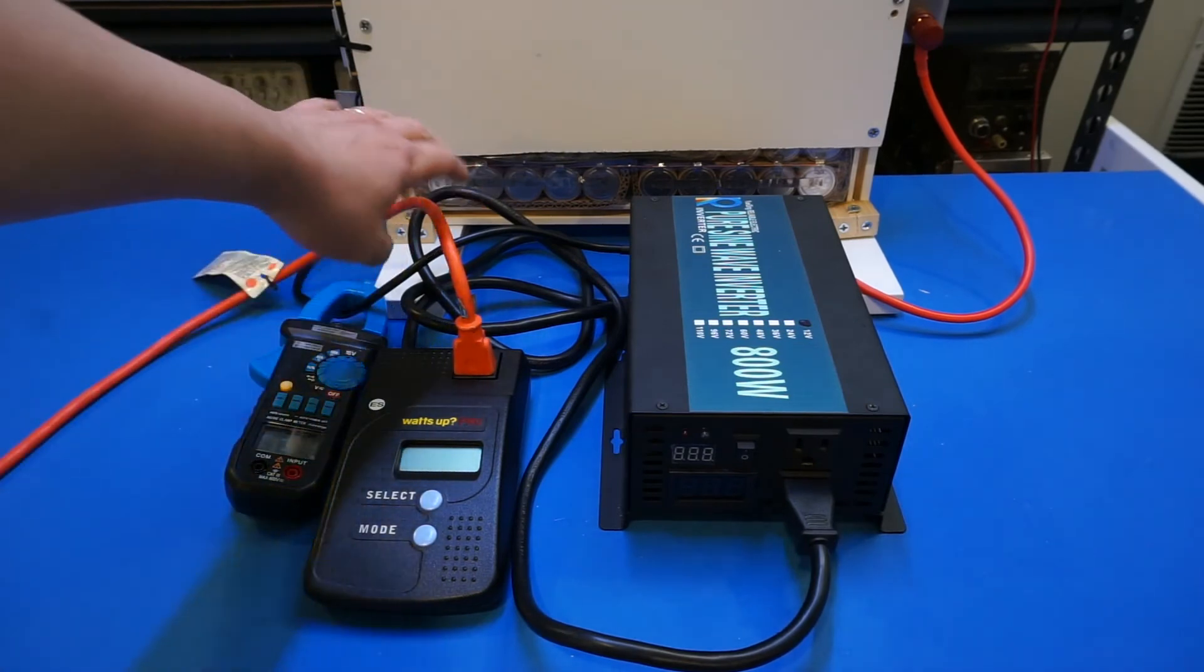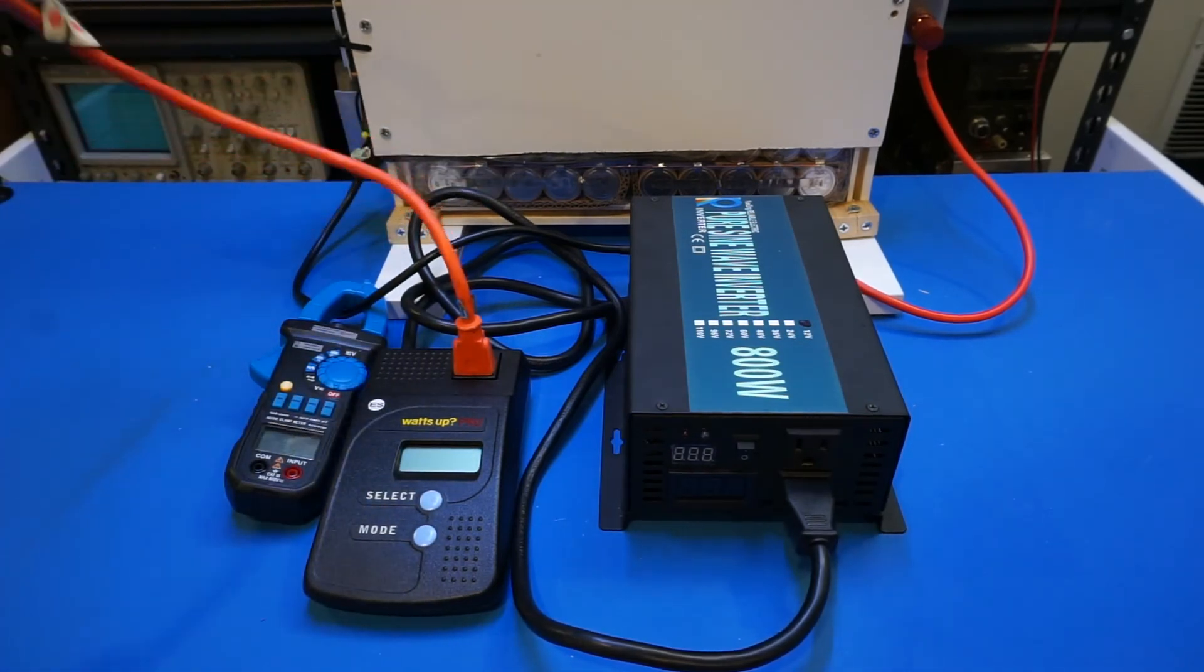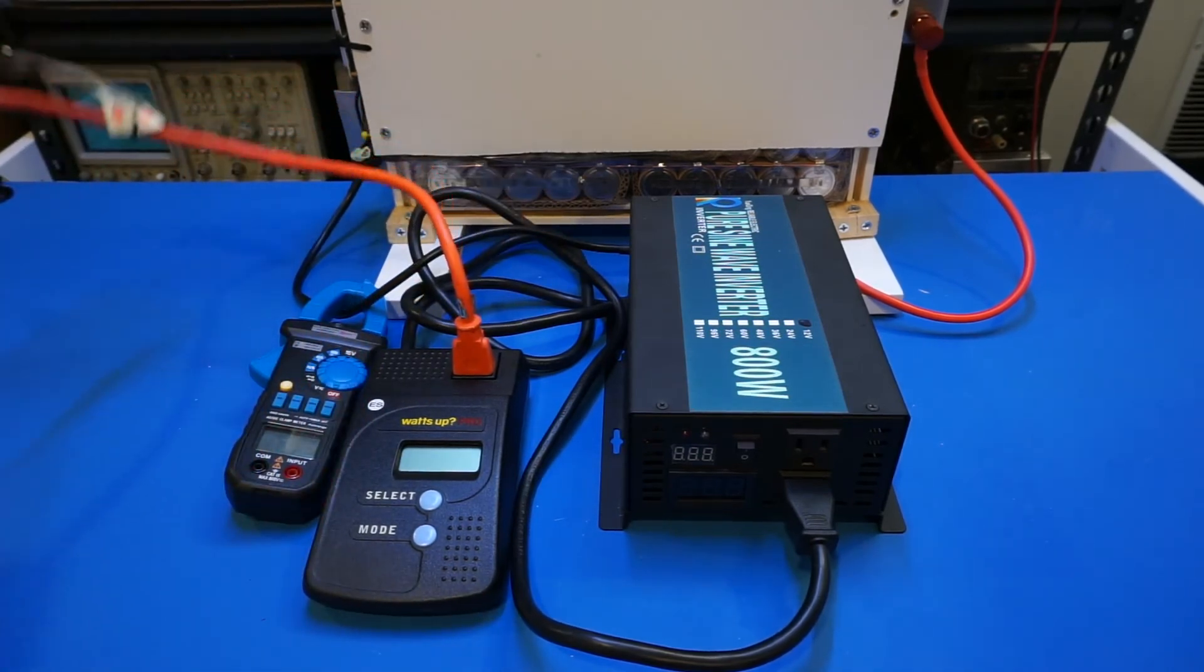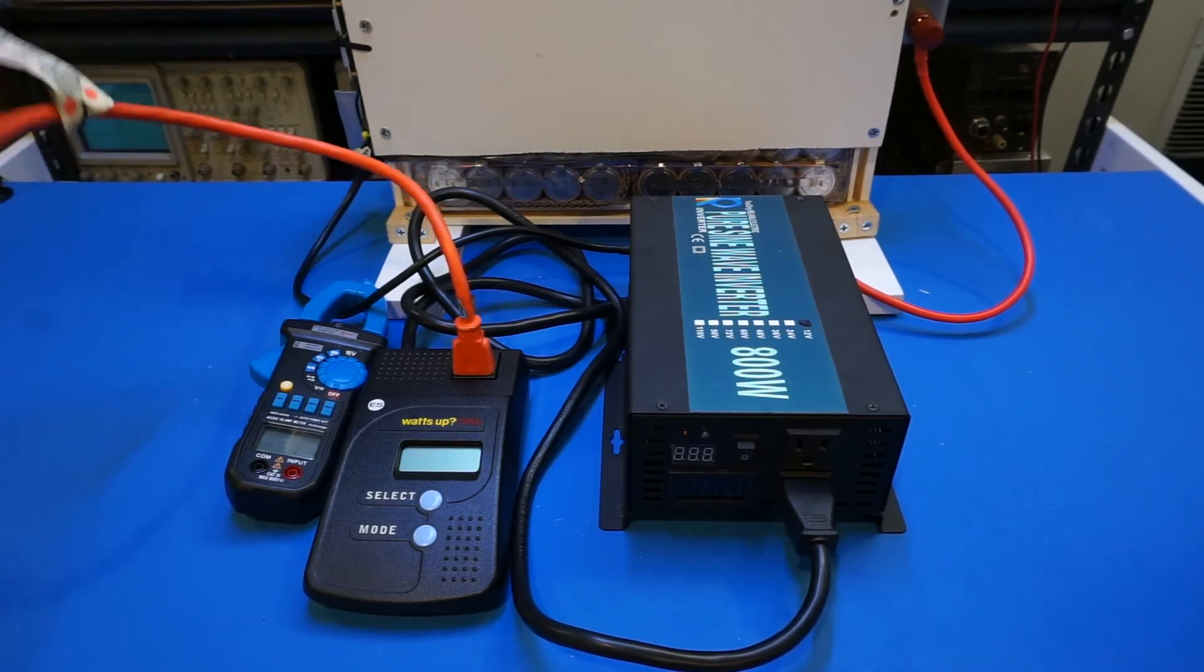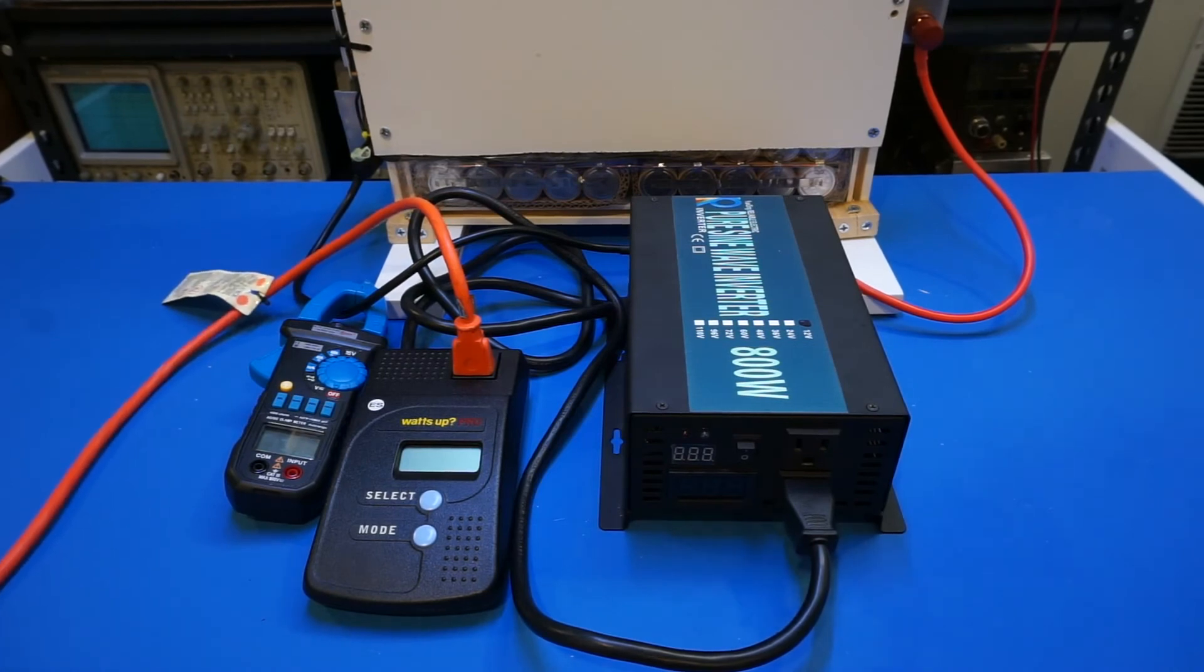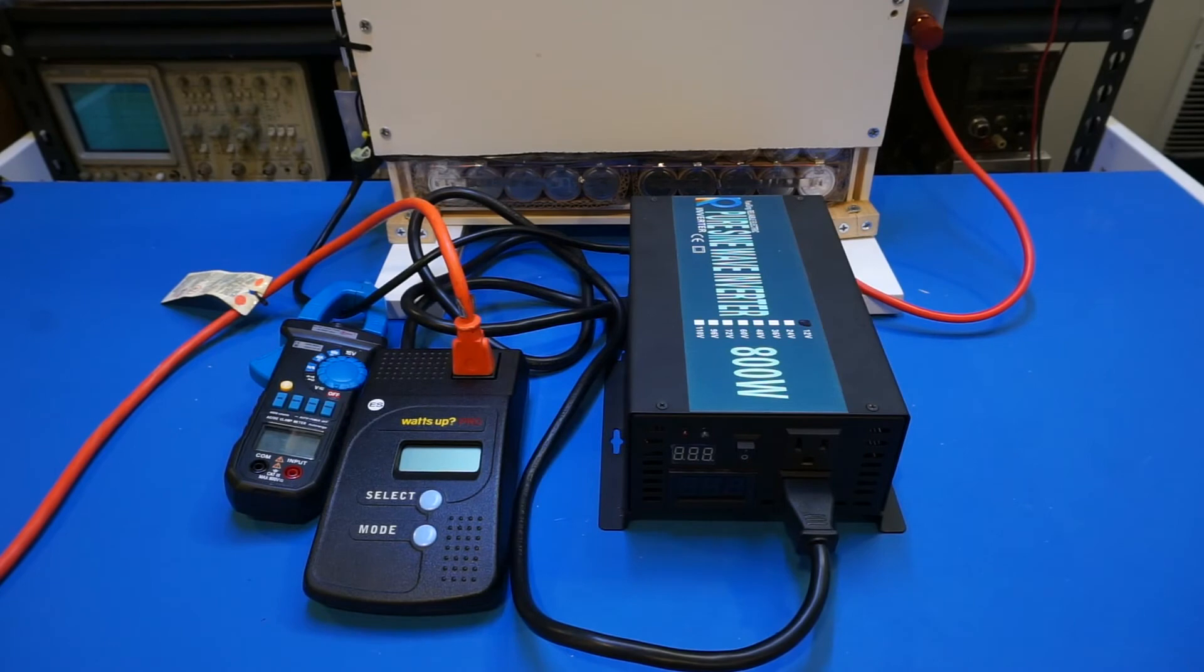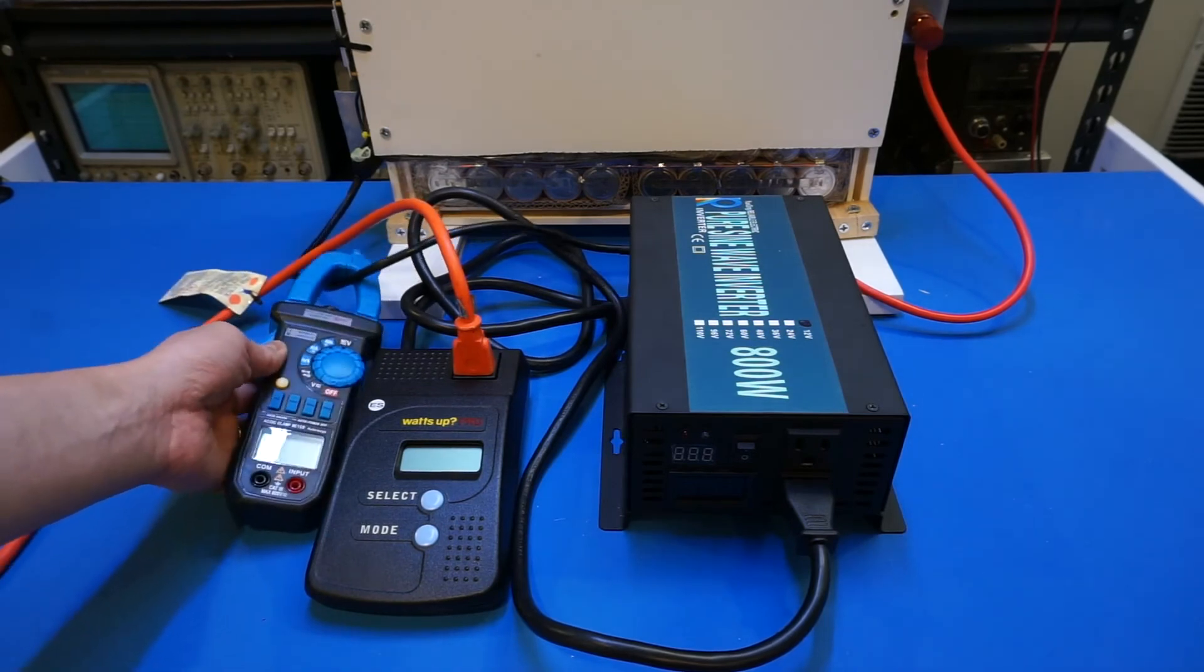And I have the outlet from this inverter into this Watts Up Pro power meter so we can monitor the connected device's wattage. And as I mentioned earlier, I don't have the cable, unfortunately it was too short. So I had to use an extension cable. This will have some voltage drop, but nevertheless, I should be able to demonstrate everything working. And on the other end of this cable, basically I used that adapter cable we made earlier with the 3-prong to the L14-30R NEMA connector and connected directly to the transfer panel. So now we want to get this whole thing started up and we'll test out how it works.